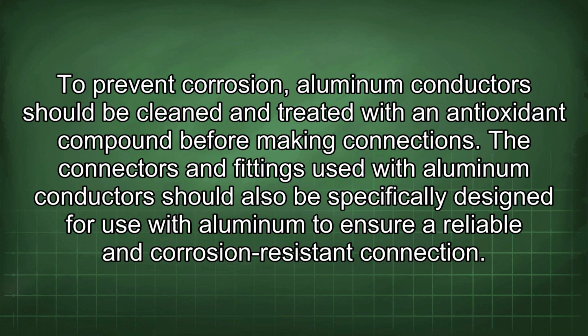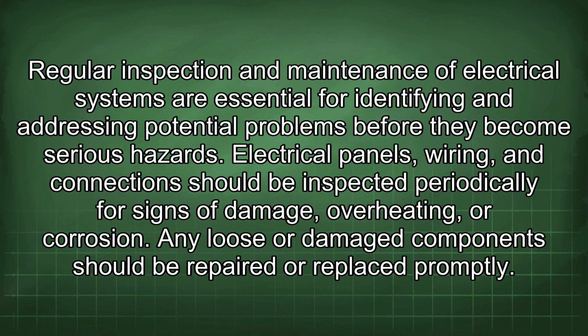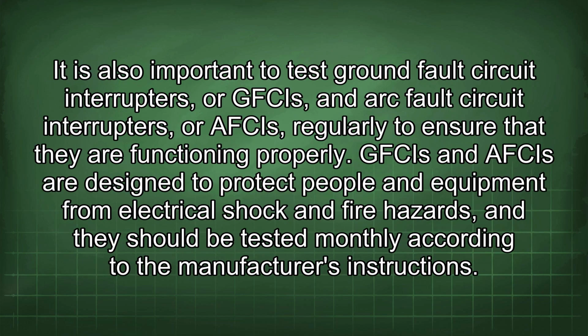Regular inspection and maintenance of electrical systems are essential for identifying and addressing potential problems before they become serious hazards. Electrical panels, wiring, and connections should be inspected periodically for signs of damage, overheating, or corrosion. Any loose or damaged component should be repaired or replaced promptly. It is also important to test ground fault circuit interrupters, or GFCIs, and arc fault circuit interrupters, or AFCIs, regularly to ensure that they are functioning properly.